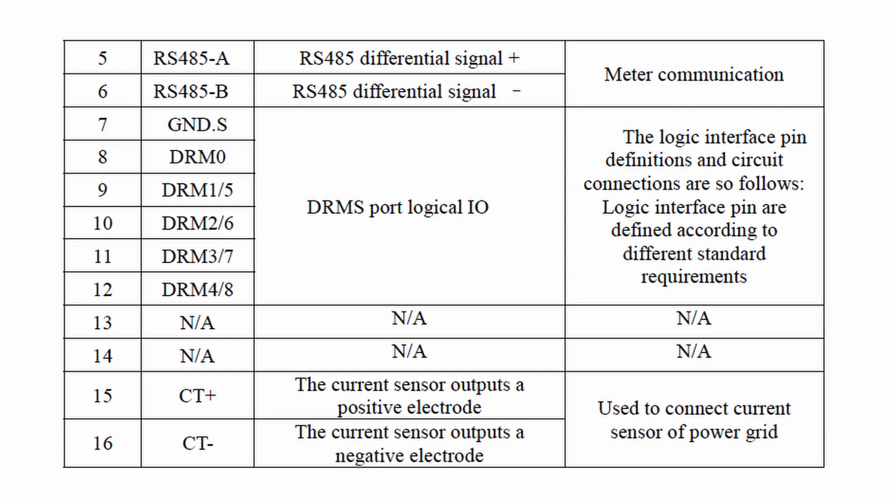If the distance is greater than 30 meters, then we have option two: meter plus CT. There is a dedicated meter and a bigger CT with 24 millimeter diameter.